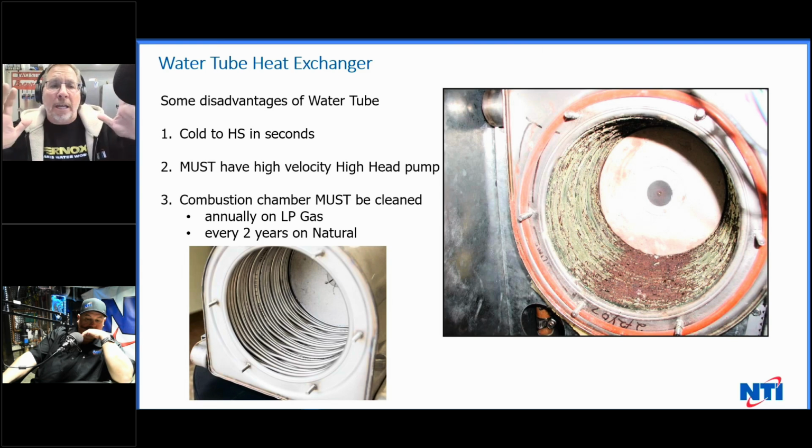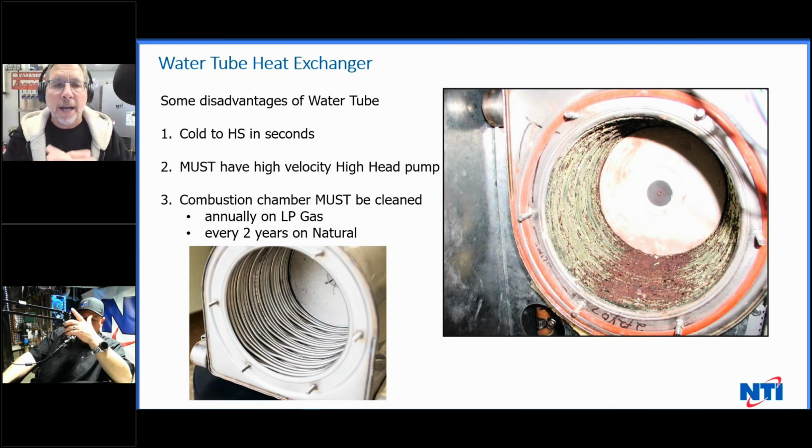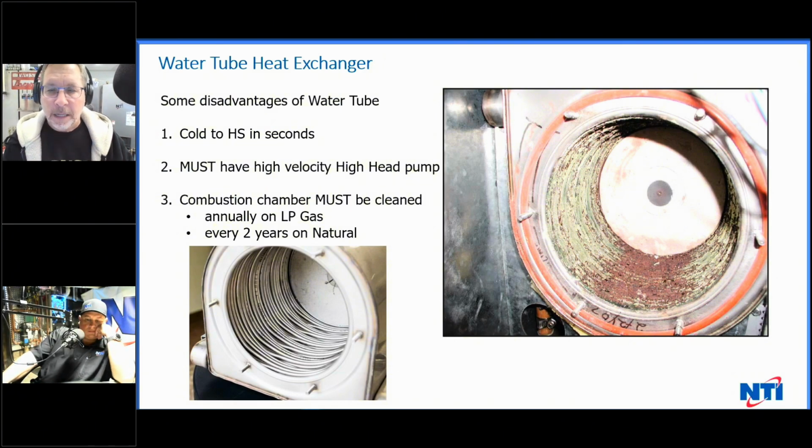to go out through the heat exchanger and go around the insulation as it's designed and go to the back. So it builds all that heat up inside there, and what happens is your stack temperature starts going up a lot. And this is why things like the thermal fuses blow on the isothermic shells. Getting rid of the fuse isn't going to help the situation. They need to be cleaned and serviced.